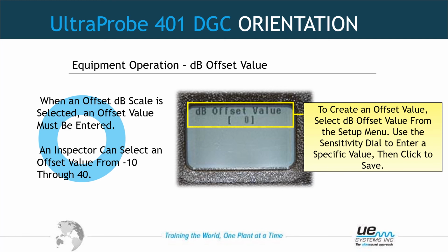So if we're going to offset it, we have to say by how much do we offset it? And you can do plus or minus. Here you have a -10 up to a +40 to offset it by. We need to offset, if you remember, by 8 dB, so a +8 dB. We want to make it read like the 10,000 was reading, 52. It's reading 44. So we'll offset it by a +8. And that's how you offset the units. And then continue on your way. You only have to do that once.